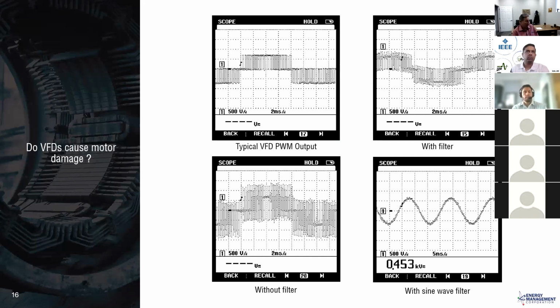So all motors are not perfect. And if there is a flaw in a motor, we were particularly concerned, from a rewind standpoint, with how we do an inverter duty rewind that's going to survive this phenomenon. We find that we can typically do a better job than the manufacturer when we use an automatic winding machine, so we have no coil overlap, when we do a strong VPI, or vacuum pressure impregnation, and we have a good structure in tying down the coils. That is what creates an inverter duty rewind for us.